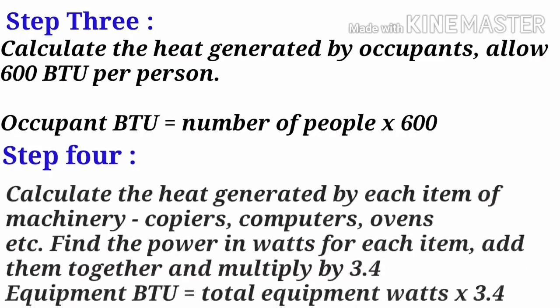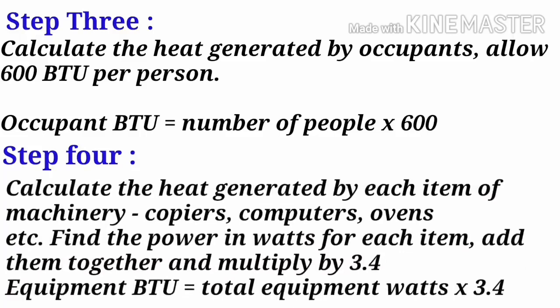Step 4: Calculate the heat generated by each item of machinery — copiers, computers, ovens, etc. Find the power in watts for each item, add them together and multiply by 3.4. Equipment (BTU) equals total equipment watts multiplied by 3.4.